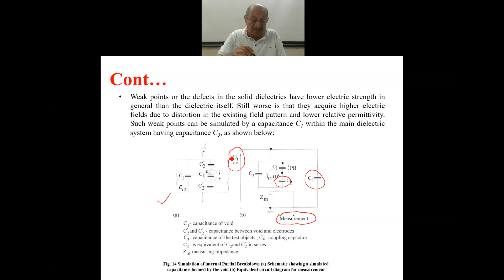And Zm, as you see here, is the measuring impedance of the circuit. For the measurement, you have partial breakdown detector equipment, so you can measure it, and you need a measuring impedance there. So I hope you have understood. This is the simulation by capacitance of the weak point and the rest of the dielectric, and this is the measuring circuit in which we are measuring the partial breakdown, applying at the terminals the AC power frequency voltage.